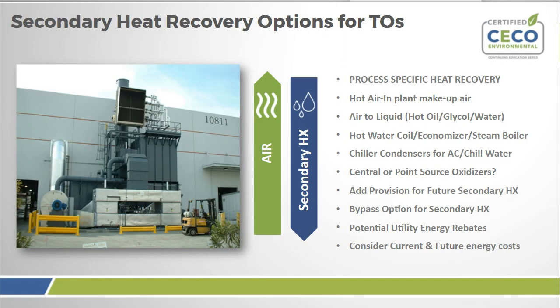Thanks, Brendan. Great job. Obviously, any oxidizer, especially like the DFTO, when you have a very high stack temperature, if you're coming in at ambient and going out at 1500 degrees on a DFTO, you have a lot of BTUs going up the stack. I know particularly in Europe and even in Asia, energy costs are a lot higher than here in the States, but most customers today do look at secondary energy recovery. It could be as simple as an air-to-liquid heat exchanger like a hot oil or glycol, or even air-to-water in the stack, a little coil.